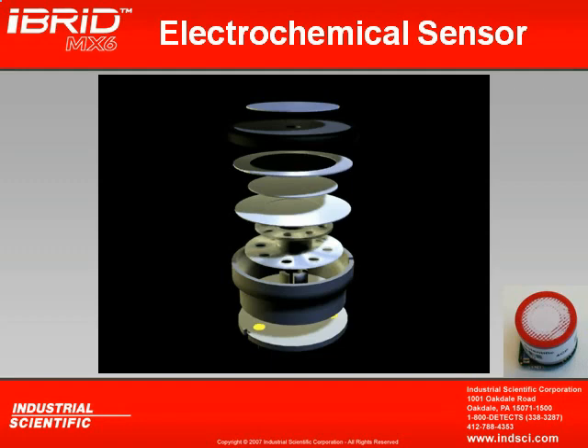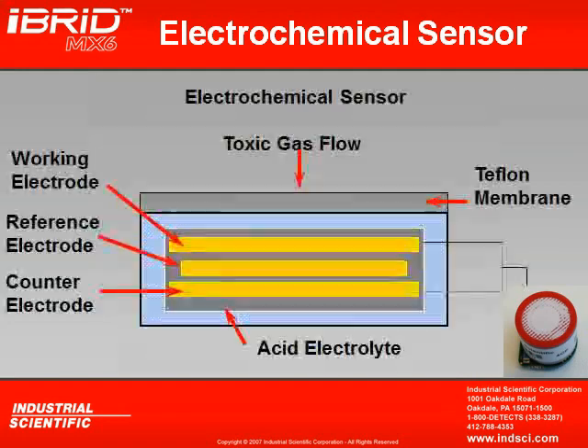Now those little electrodes are actually Teflon coated metals. And the metals that are used are metals like gold, tin, platinum, silver, all dependent upon the type of gas it's designed to detect. In other words, the only difference between an SO2 sensor and an H2S sensor is the metal plates inside. So what we're looking at here is the cross section of the sensor. And as you'll see, once again, we have our metal plate sitting in an acid bath.